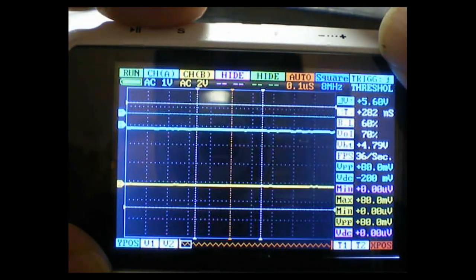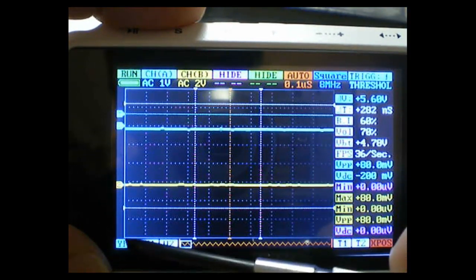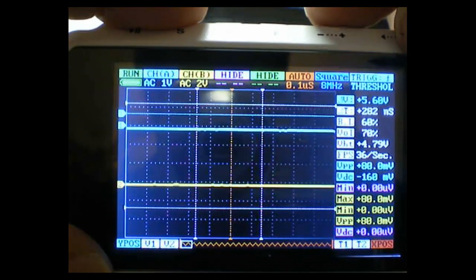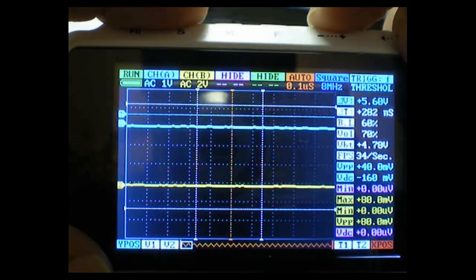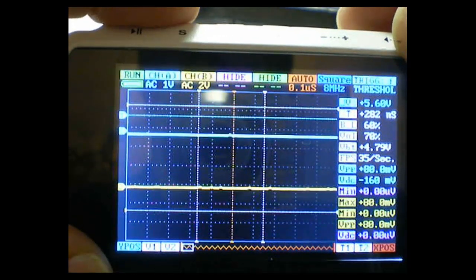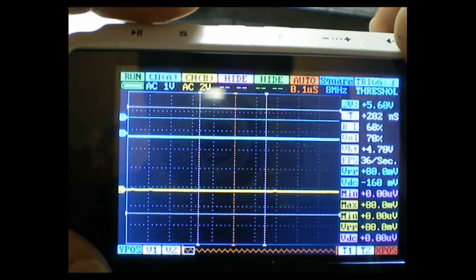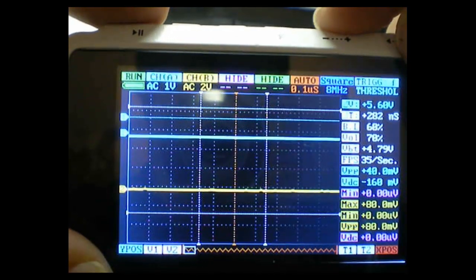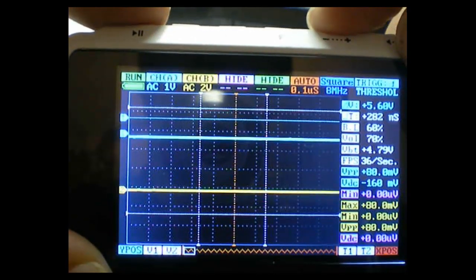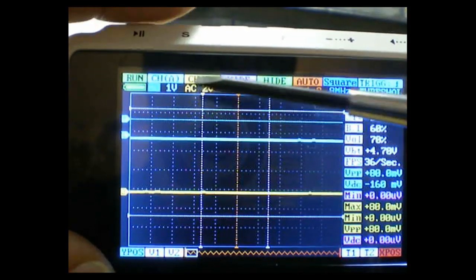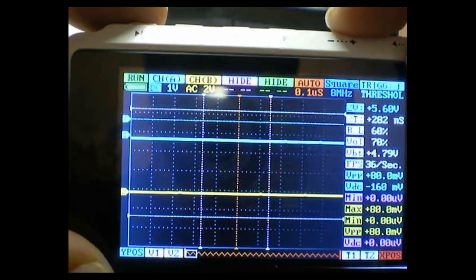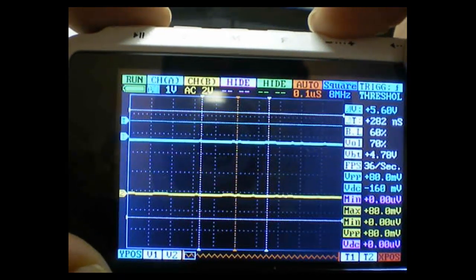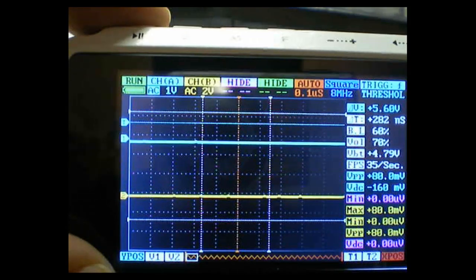If I hit the S key, I'll step down here, way down at the bottom, the vertical position. And now I can move the plus or minus jog key. You can move the waveform up or down. If I step again, that brings us back up to A. And here I can, with the plus or minus, I can hide it or enable it. There's only two choices. If I step again, we're down here on the input coupling. Right now it's AC. With the plus or minus jog, I can make it DC or AC. So that's how you operate these functions on the channels A and B.